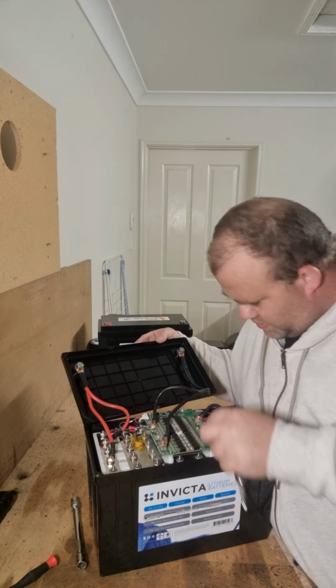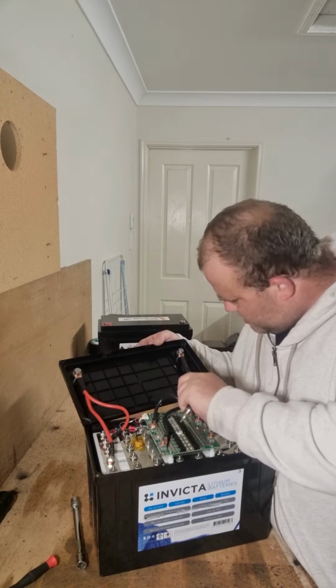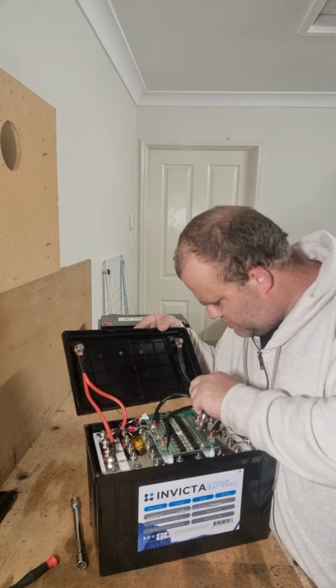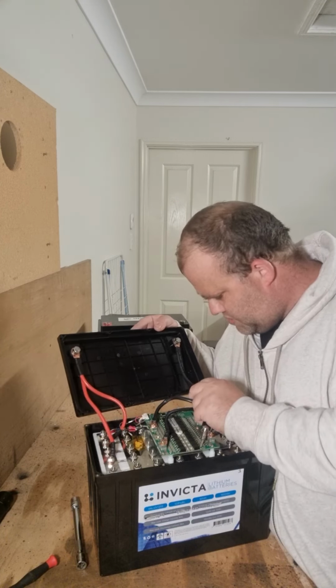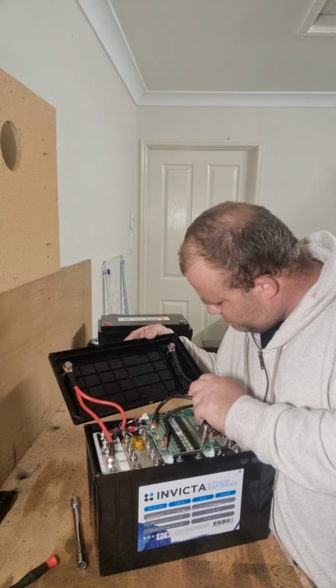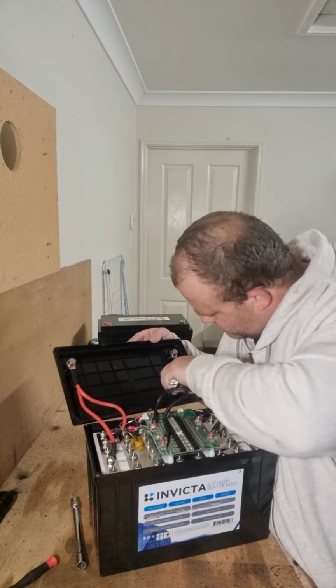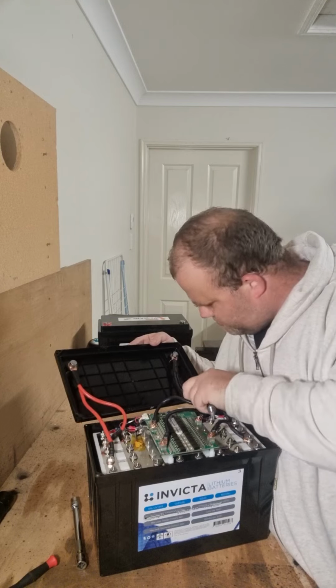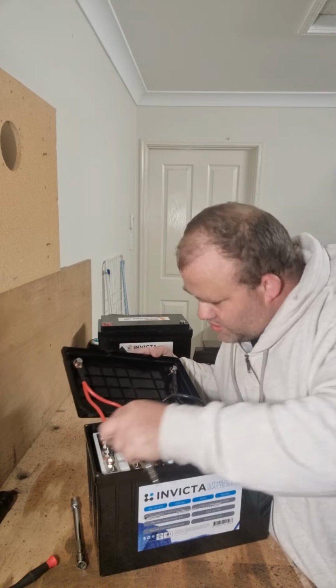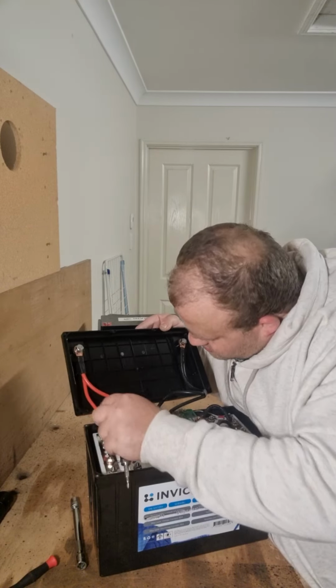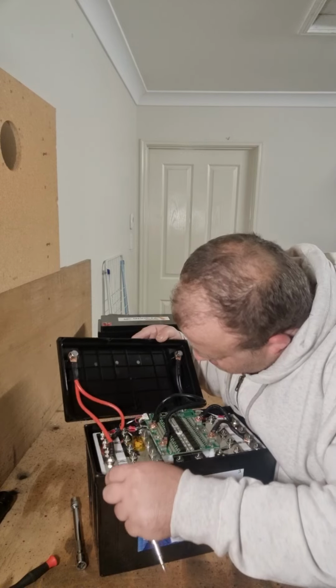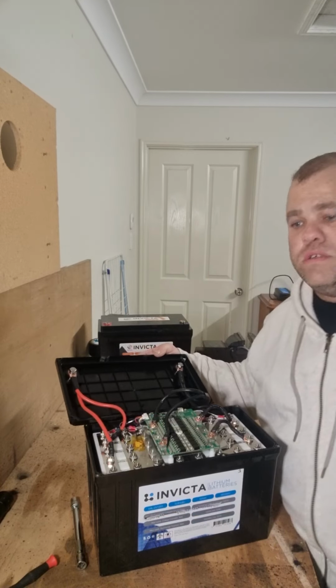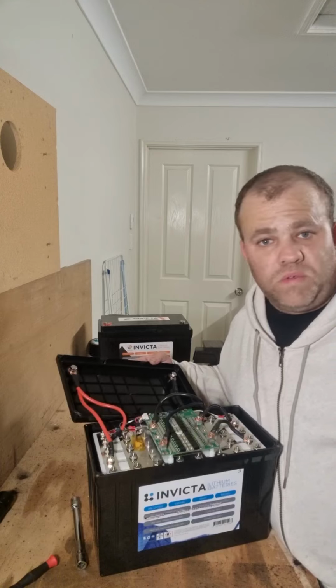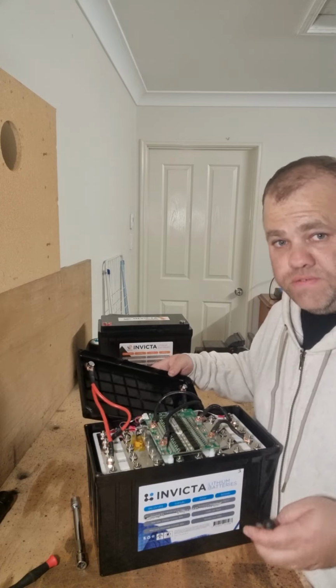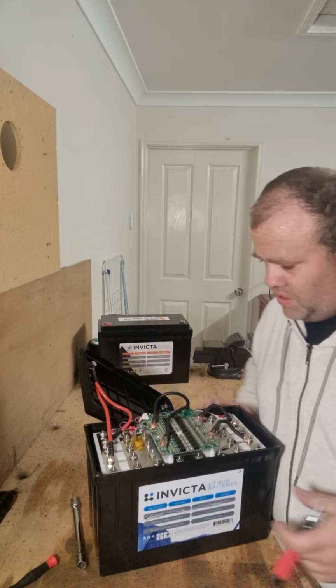And the wiring is, what do we got here? Looks like it's capable, doesn't say, the gauge is quite covered. Maybe I can get it on the positive side. It's an 8 gauge wiring, so well within the specs needed for the 95 amp draw as well.